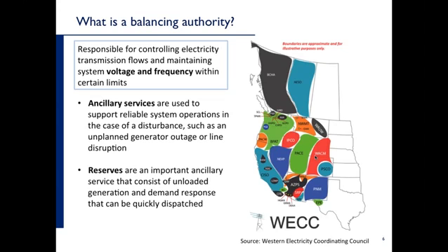And then finally we have reserves. A reserve is essentially either a generation or it could be a demand response resource that's not fully loaded and can therefore respond to imbalanced situations. So for example, if you find that demand is going up and you have a unit that you can move up, or maybe a better example would be you have a unit that disconnects offline, you have a reserve, which is an unloaded capability of a unit that can be brought up to replace the unit that trips offline.